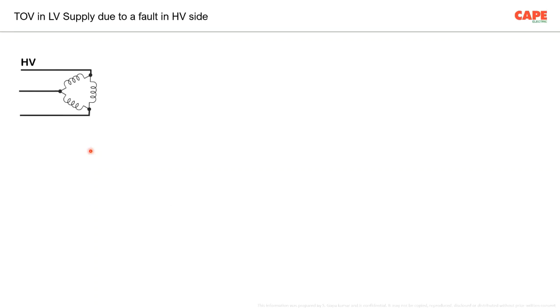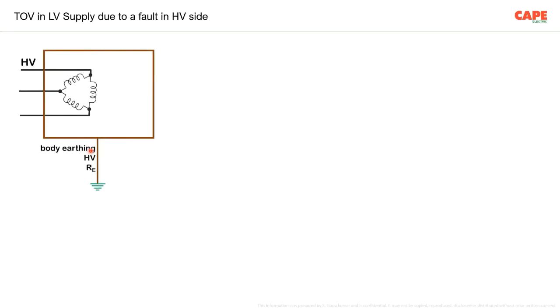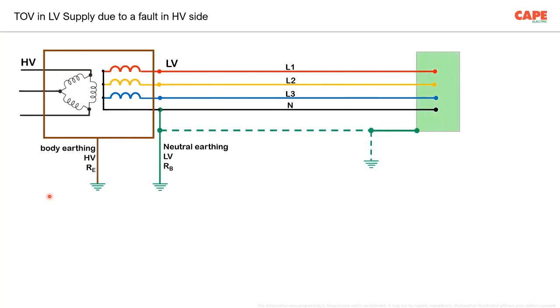I'm just showing a picture. High voltage side of a transformer, body of the transformer which is connected to an earth electrode. You have the secondary side of the transformer, neutral of the transformer is connected to a separate earth electrode. You have the electrical installation. There are two dotted lines you can see here. This denotes a TNS system and the second one denotes a TT system.